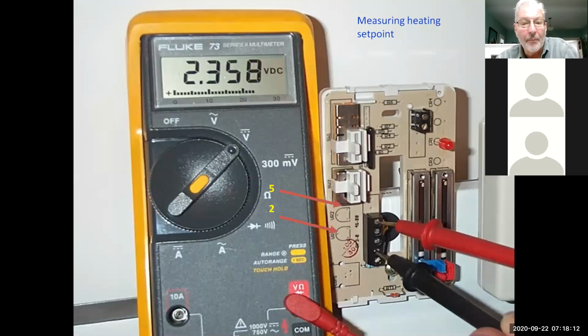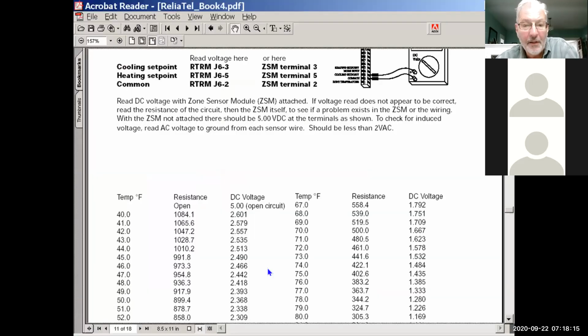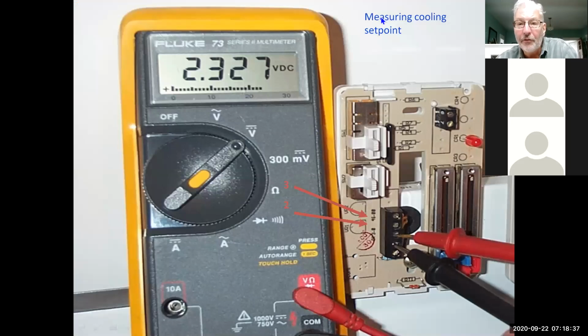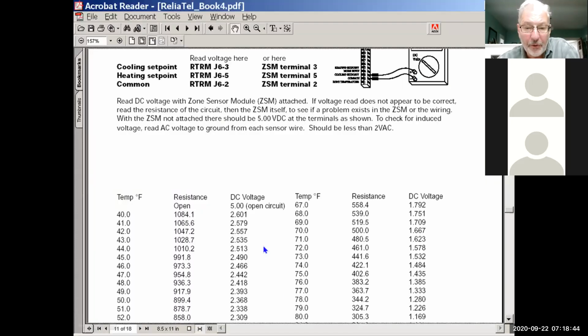And if I read, I'll jump back here, 2.358 volts DC is roughly in here. So you're looking at a temperature of roughly 50 to 51 degrees is what that's telling us. If I go to the cooling set point, like it shows here, and I read 2.327 volts on the chart, that is somewhere in here. Again, the thermostat is set for about 51 degrees, somewhere in that area.